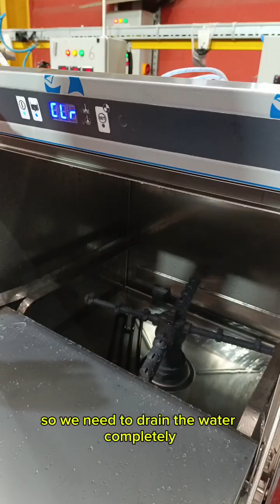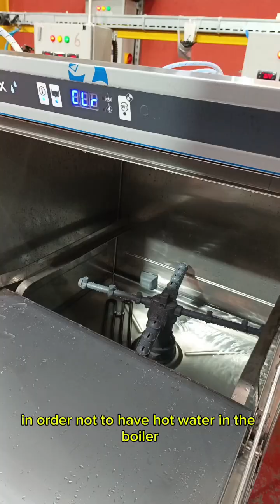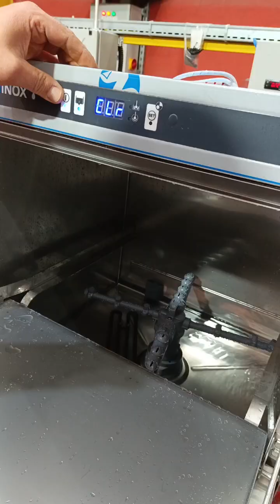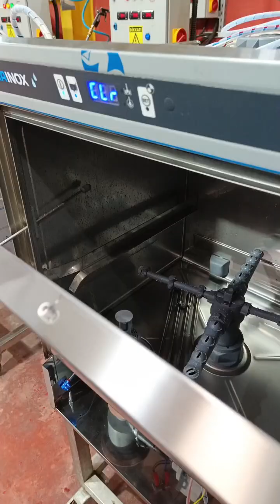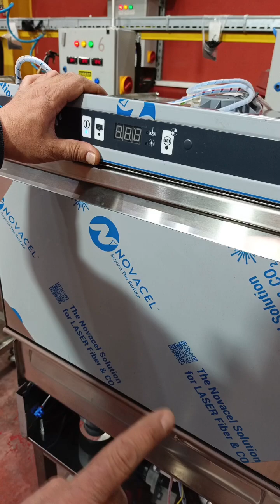We'll get NTC and resistance failure again. So we need to drain the water completely, in order not to have hot water in the boiler. We will empty the water completely. Now let's fill the machine with water again to cool the hot water in the boiler. We will give cold water to the boiler, because the hot water would flow out when changing the NTC.